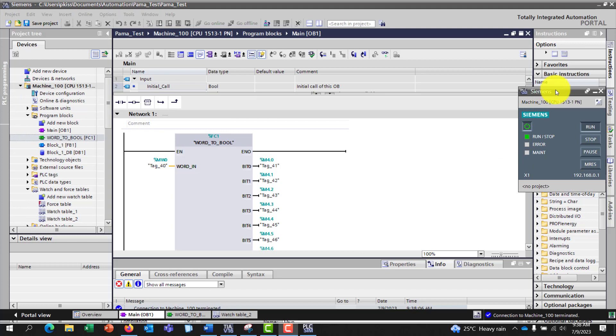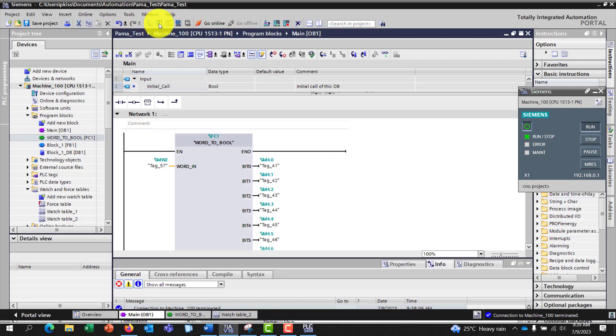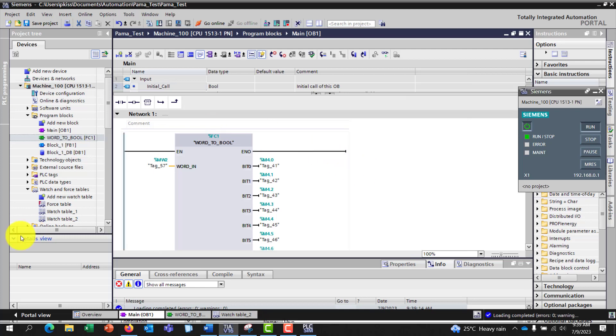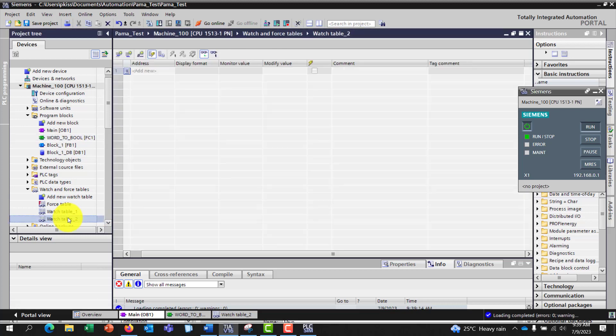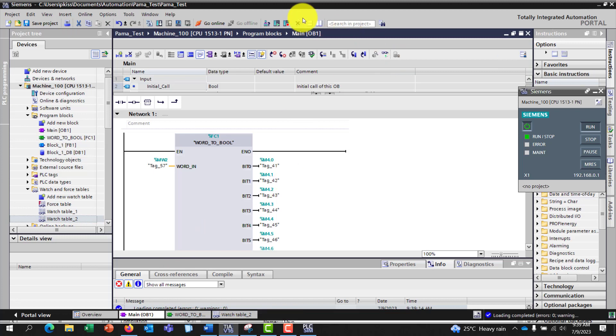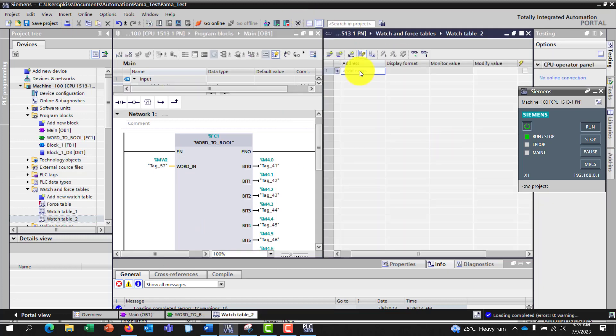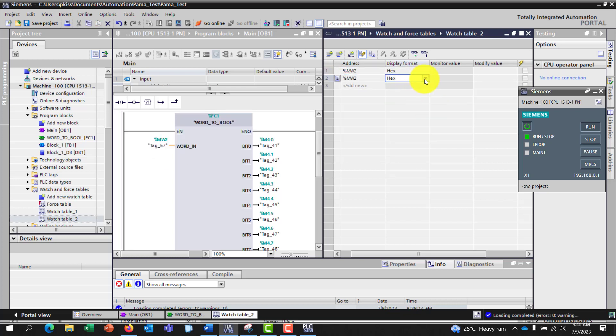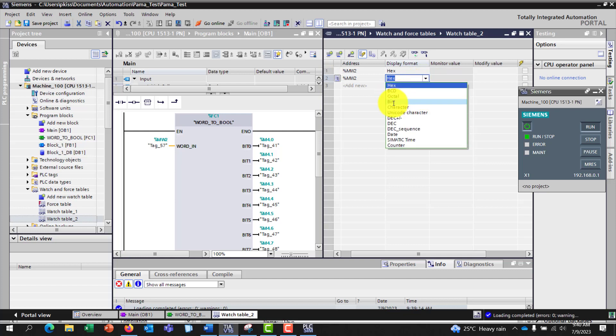The simulator is started. After opening the simulator I need to make some changes — I've used MW0 for my clock memory so I have to change this to MW2 for this test, then download again. With that done, I bring up my watch table — I have an existing watch table and double-click to open it. I put them side by side. My address to modify is MW2. I change the display format to binary so we can see how the data changes, and the other section in hex.